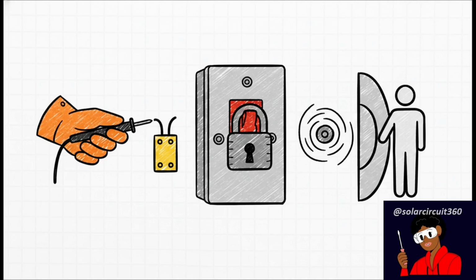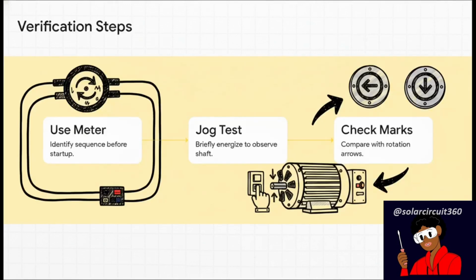And when you are performing startup tests, you've got to keep yourself, your tools, and your team completely clear of rotating shafts, belts, and couplings. Safety first, always. Okay, with safety established, here is the exact step-by-step verification method the pros use to solve this mystery safely in the field. Step 1 is using a phase rotation meter. This thing is your best friend.